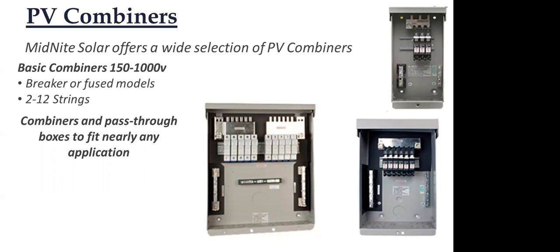Oh, I lost my mouse. Well, you might just have to believe me on that. I can't get my mouse back. There's a little plus emblem on the bottom of each breaker. And yeah, right there. There's a little plus emblem there, and that is a side with the greatest potential. So that's coming from the PV array. So the power is coming in here, going through the breaker, through the bus bar and over to the charge controller. So now if this string here shorts out, these 2 strings are ganging up on it. The current's flowing back this way to try to gang up on that, and this is going to open under load in a reverse polarity situation.